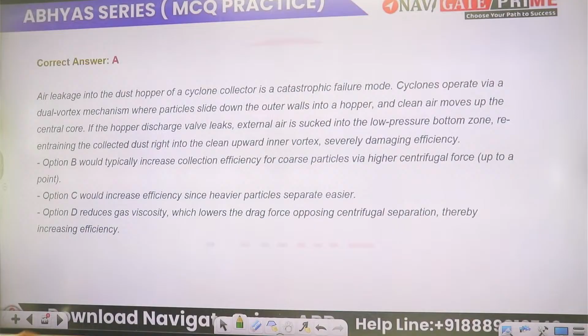The air leak at the dust hopper of the cyclone is catastrophic. A cyclone works via a forced vortex system, where the particles slide down the outer wall into the hopper and the clean air moves up the central core. If the hopper discharge valve leaks, external air is sucked into the lower pressure bottom zone.